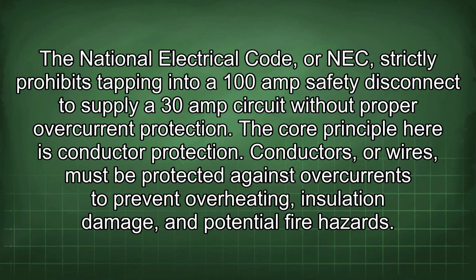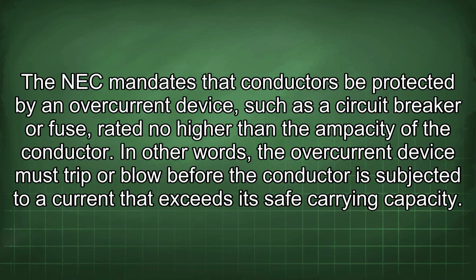The National Electrical Code, or NEC, strictly prohibits tapping into a 100 amp safety disconnect to supply a 30 amp circuit without proper overcurrent protection. The core principle here is conductor protection. Conductors, or wires, must be protected against overcurrents to prevent overheating, insulation damage, and potential fire hazards. The NEC mandates that conductors be protected by an overcurrent device, such as a circuit breaker or fuse, rated no higher than the ampacity of the conductor.